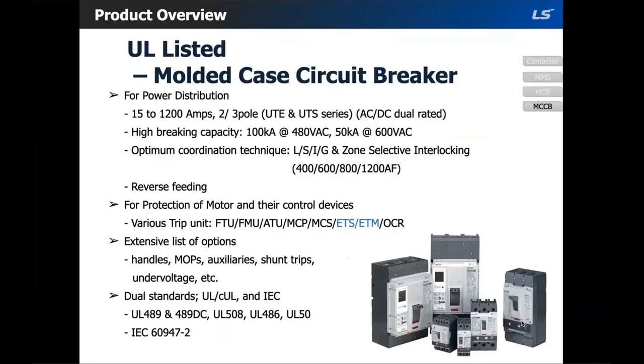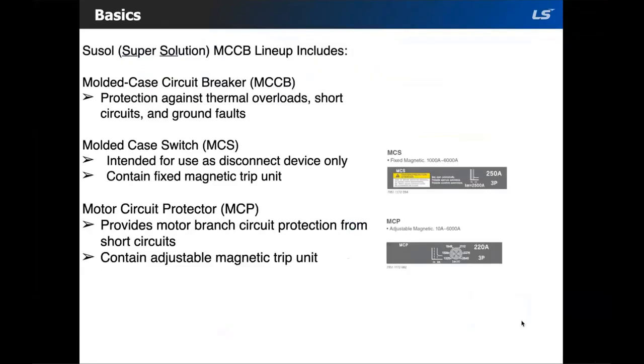Okay, so let's go into the MCCBs. Okay, I'll update you too, Andy. So within the UL MCCB family, there are three types of breakers. So there is the MCCB, with protection against thermal overloads, short circuits, and ground faults. We also offer the MCS, which is a molded case switch, intended for use as a disconnect device only and does not provide overcurrent protection.